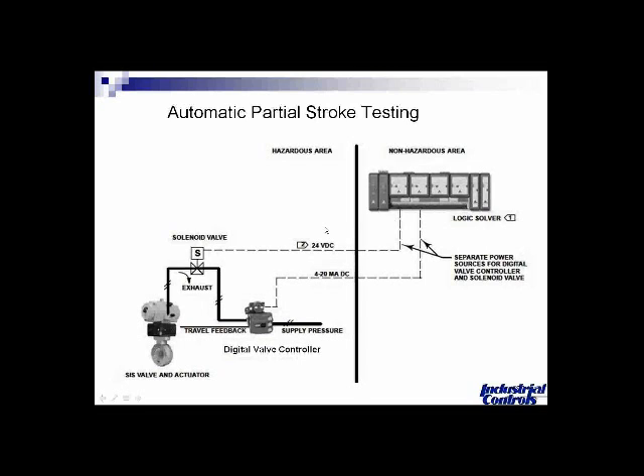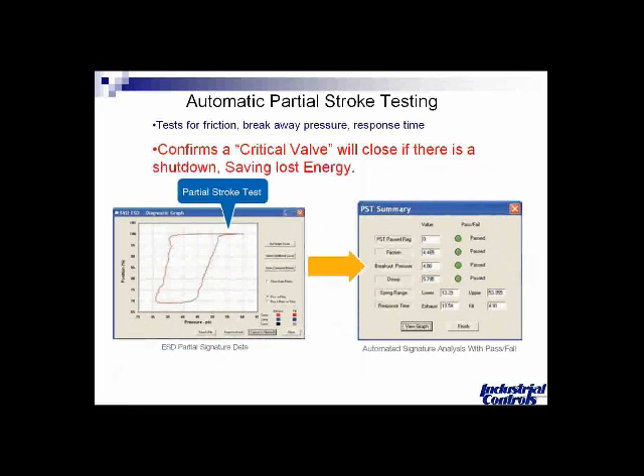I mentioned going down to about 70%. In some cases in a process chemical plant, maybe at night, they don't run the full range of the process. So that would be a good time to have it pre-programmed to automatically take selected valves. They can be done one at a time or however you choose to do it. And you can see in this graph here, this took a valve that was fully open, and it took it down to about 70% open and back.